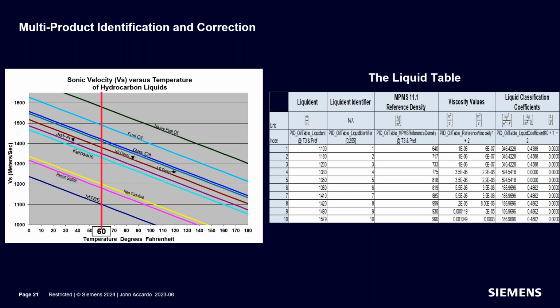So by knowing what the temperature is, and by knowing what the actual speed of sound is, we can use that slope factor to calculate what that speed of sound would be at 60 degrees and positively identify that liquid. And so each entry in this table on the right is the speed of sound at 60 degrees for a range of products, and what the viscosity is and what the density is at 60 degrees for each of those products.